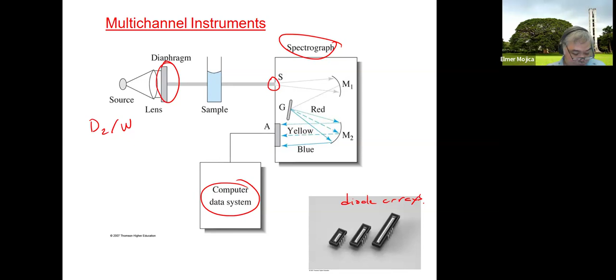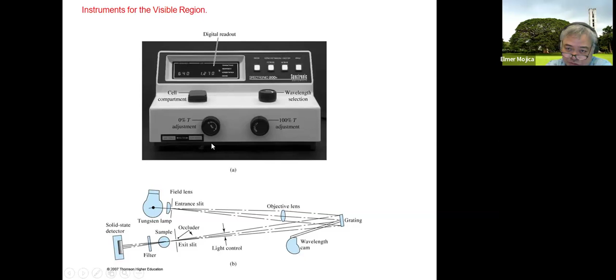So if we're going to look at some of the specific things, so ito yung Spectronic 20. So it's a digital readout. Okay. So if you're going to look at the schematic diagram that we have here, so usually it's a tungsten lamp. Okay. So you use it for visible region. So there's a field lens there and there's a slit. So you select what wavelength you want the tungsten lamp to have. Pass to the objective lens, the gratings, the wavelength, the light control, then exit slit, go to the sample, and then the filter, and then you have a detector that you have.